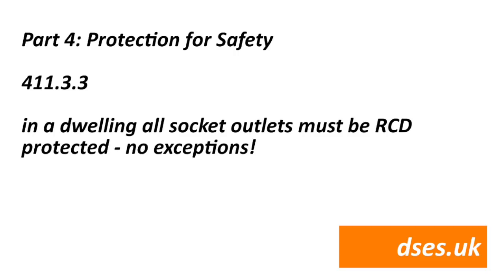Regulation 411.3.3 has also changed: in a dwelling, all socket outlets must now be RCD protected, with no exceptions — unlike before, where a label could be used to indicate a given outlet was not RCD protected and was for a specific item of equipment only. I'd prefer to still have the label exception, as I used it for installing sockets for Freeview aerial boosters in the attic using class 2 devices on unprotected lighting circuits. Now I either have to cut off the plug and install it on a fused spur, or install an RCD socket accessible enough for its test button to be operated. Exceptions are still permitted for non-dwelling installations, but a documented risk assessment must be produced between the site duty holder and the appointed electrician.